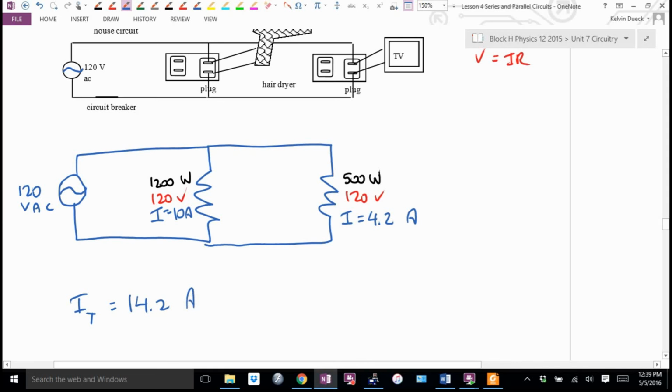We're close. In fact, something this close, you may actually end up tripping it after a time delay, because as the wires heat up, that actually does increase their resistance. In our magic physics world, this doesn't happen, but in real life, it would add another built-in resistor, and it might cause the current to go up a tiny bit more. This is why sometimes the breaker doesn't blow right away, it blows after a few minutes.